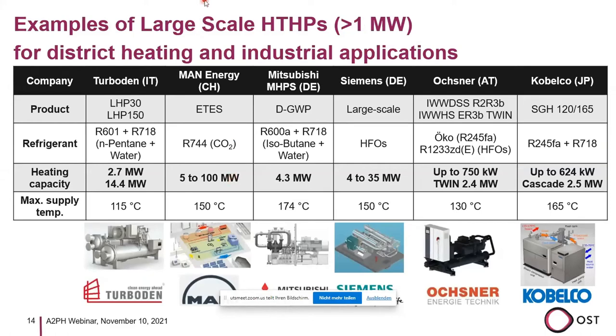Then there are several large-scale heat pumps which have a capacity larger than 1 megawatt for district heating and industrial applications. So here you see the names or the brands. So Turboden, Italy, MAN Energy, Switzerland, Mitsubishi in Germany or Japan, Siemens, Ochsner or Kobelco. So what you see here, the capacities, and there are options to cascade the heat pumps, several in parallel, to increase the heating capacity also to the megawatt scale for Ochsner, for example, or Kobelco. And the temperatures they can reach are here all above 100 degrees, up to 174 in this case.